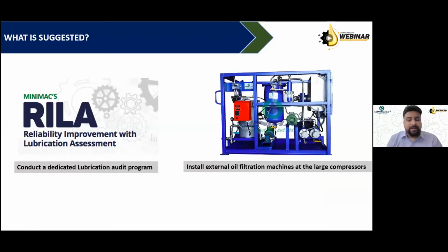We have been visiting a lot of refineries, oil and gas platforms and processing stations where large sized compressors are there, and the problems of these compressors are also very different. In those cases, we have identified that the foreign particles entering the lubrication system are very high.